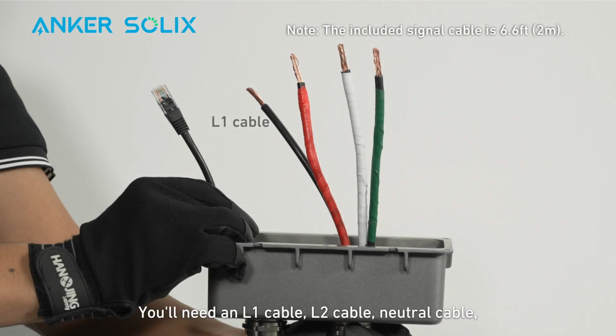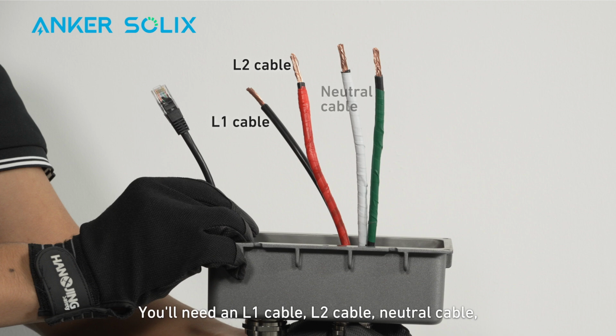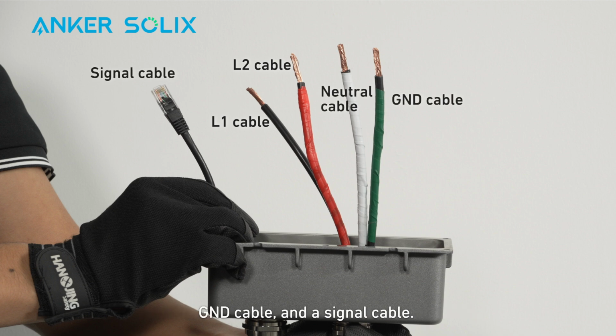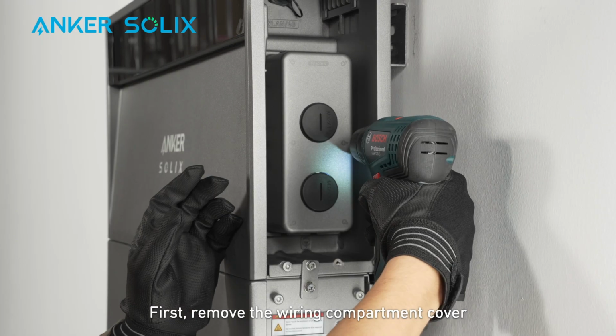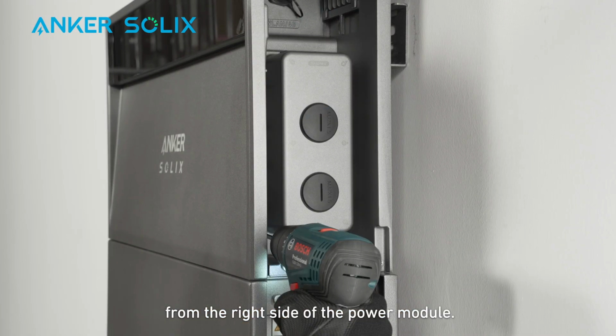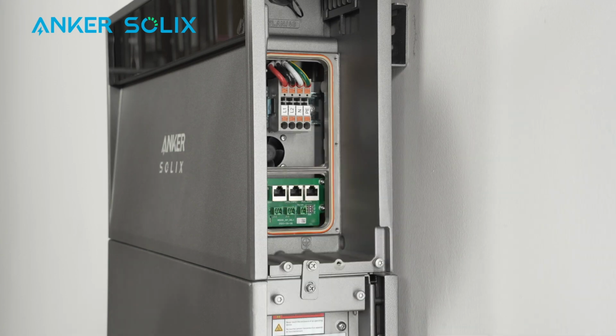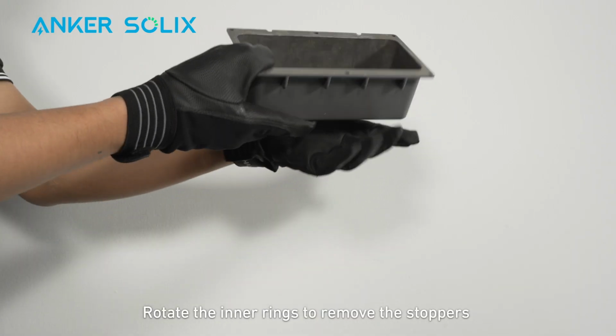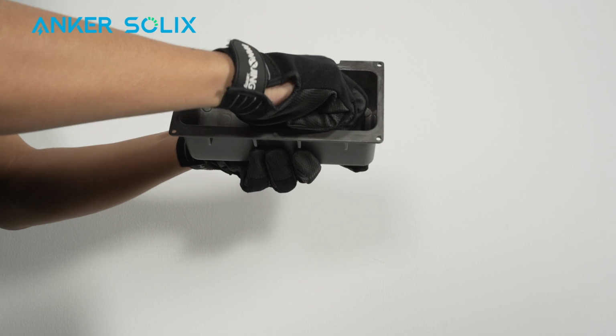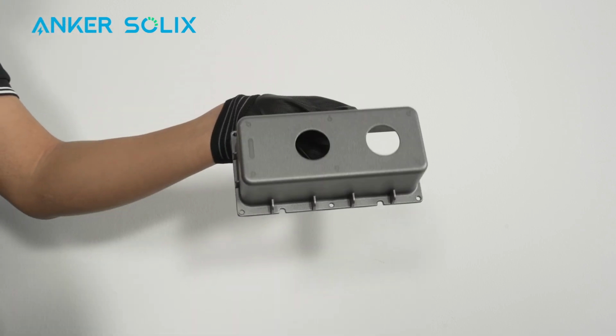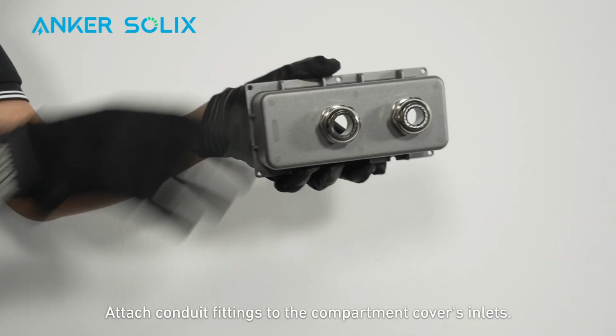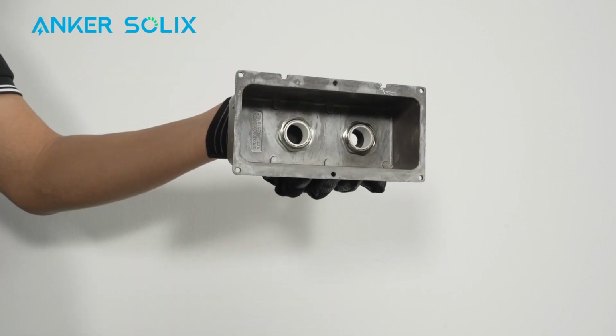You'll need an L1 cable, L2 cable, neutral cable, ground cable, and a signal cable. Make sure the signal cable is the appropriate length. First, remove the wiring compartment cover from the right side of the power module. Rotate the inner rings to remove the stoppers from the compartment cover. Attach conduit fittings to the compartment cover's inlets.